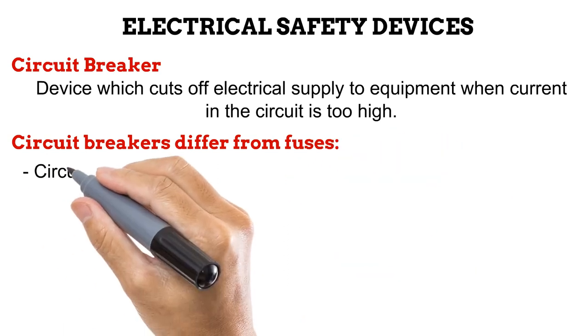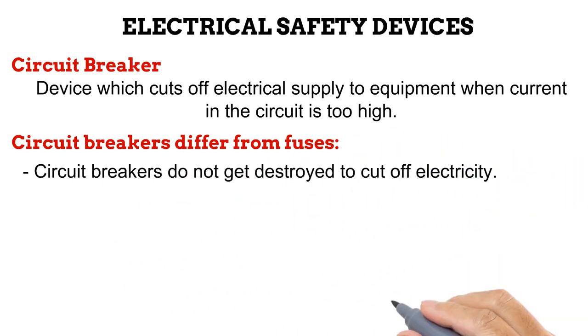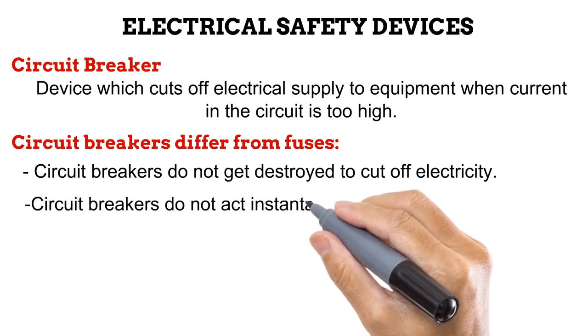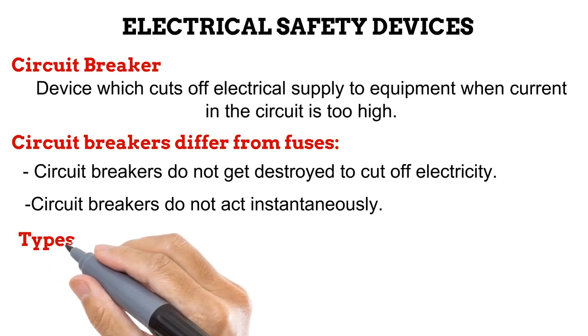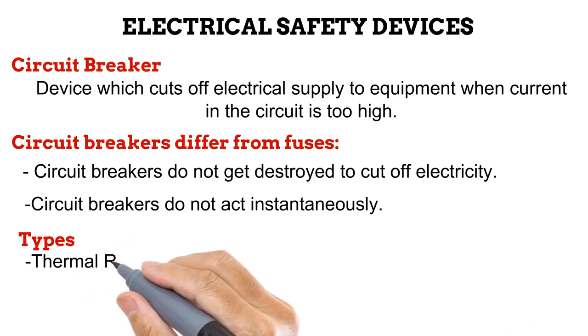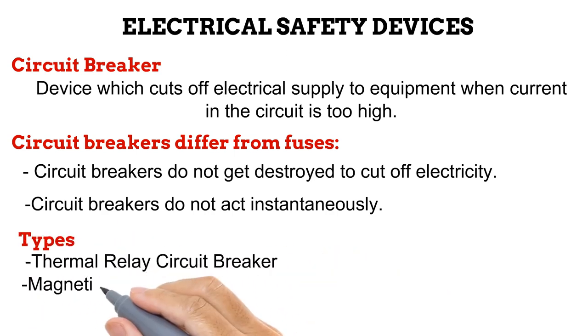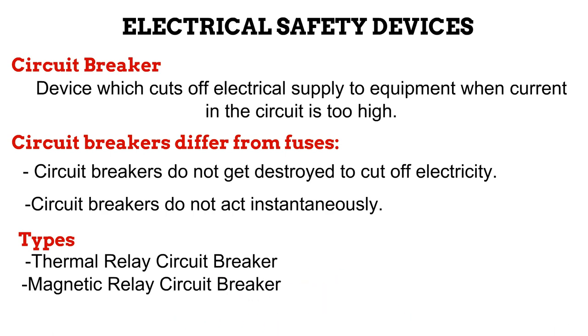Unlike the fuse, the circuit breaker does not melt or get destroyed to perform its protective function. Also, while fuses melt as soon as dangerous current enters the circuit, circuit breakers do not act immediately — they allow high current to flow for a while before cutting off the supply. The two common types are the thermal relay circuit breaker and the magnetic relay circuit breaker.